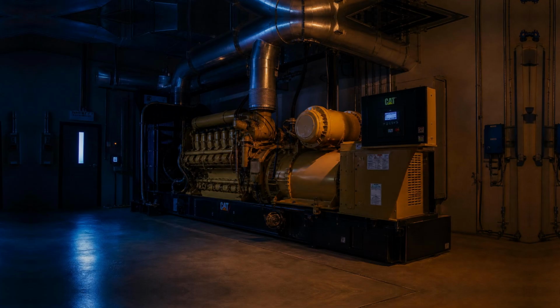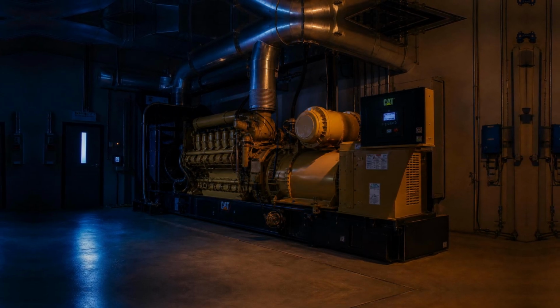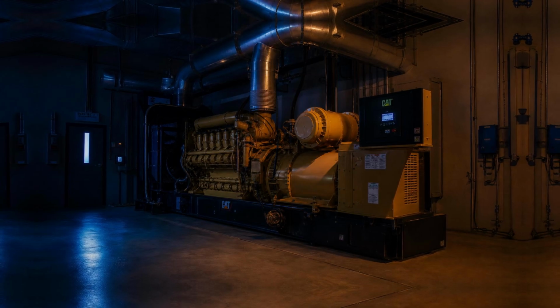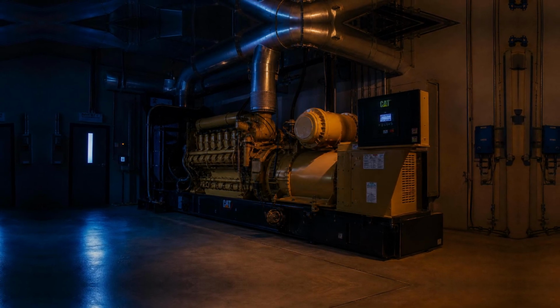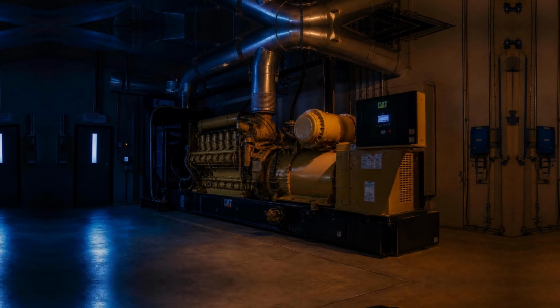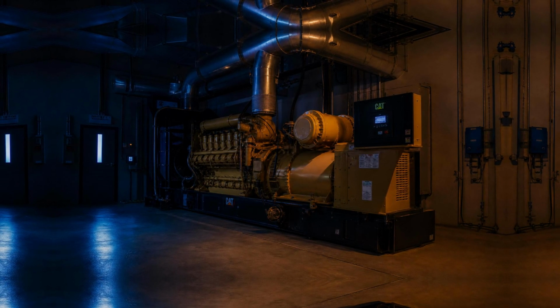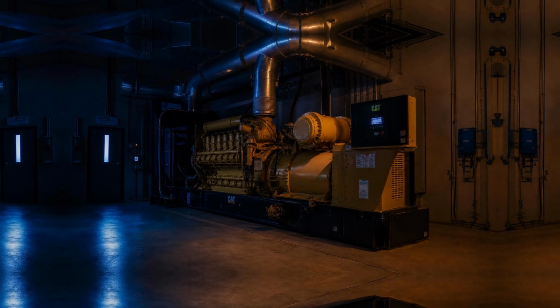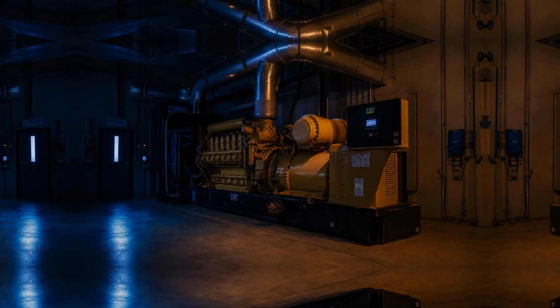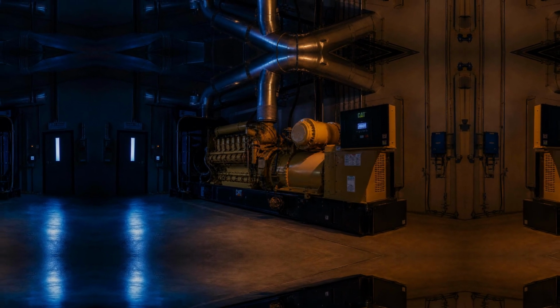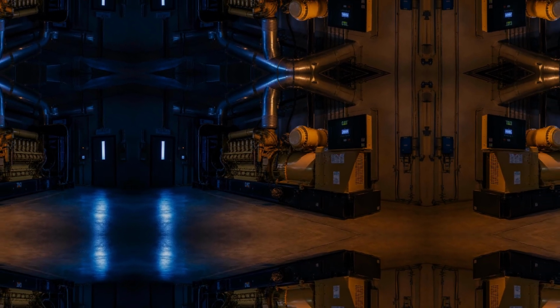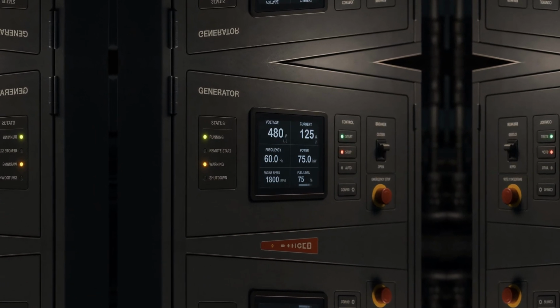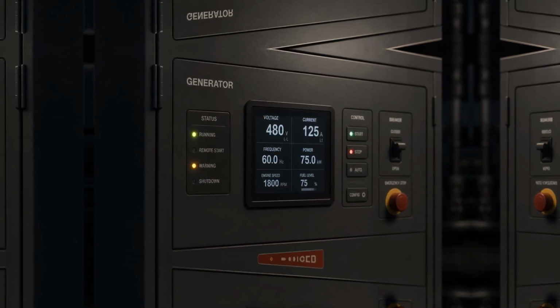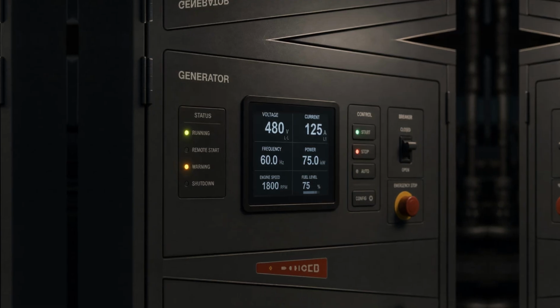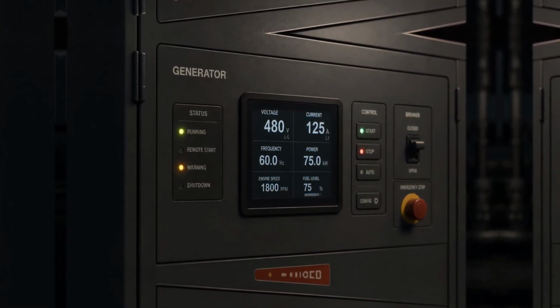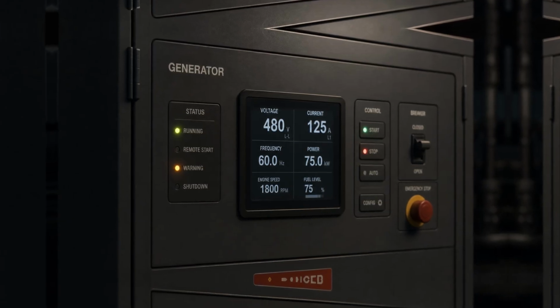It is not designed to power a building through a long outage the way a generator can. It serves a different and more specific role: to ensure that in the seconds, and sometimes the minutes, when neither the utility nor the generator is available to serve a particular load, something is. Continuously, without interruption, without so much as a flicker. The UPS accomplishes this through a combination of components working together, and it is worth spending a quiet moment with each of them, because together they form a picture of a system that is, at its core, about the patient accumulation and careful release of stored energy.